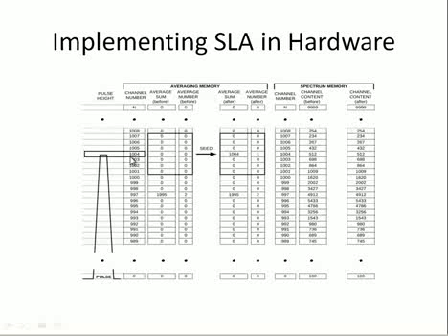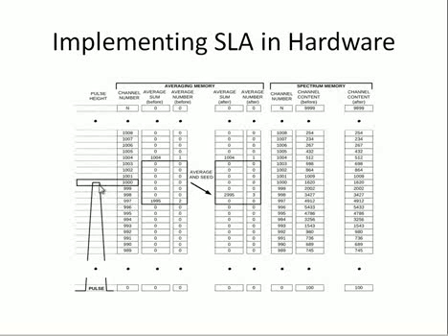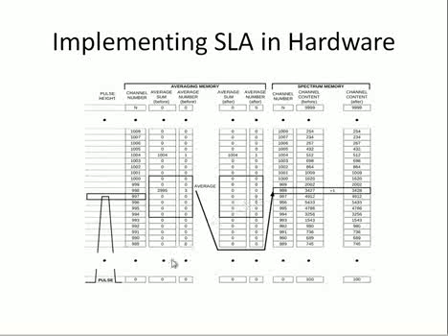If we get a third pulse height, maybe it's off to the side here, so it has no averaging windows, so it starts a new averaging window. Maybe we look at our fourth pulse height, it comes in here, so we have to average it with this averaging window, and we increment the count by 1 again. And suppose that for this particular example, we've chosen to average 4 pulse heights. So once this fourth pulse height comes into this averaging window, instead of just incrementing the count by 1, we set everything to 0, and we actually output a single count into the spectrum memory. So this is what the post-process spectrum is going to look like. So that's how one could implement SLA in hardware.